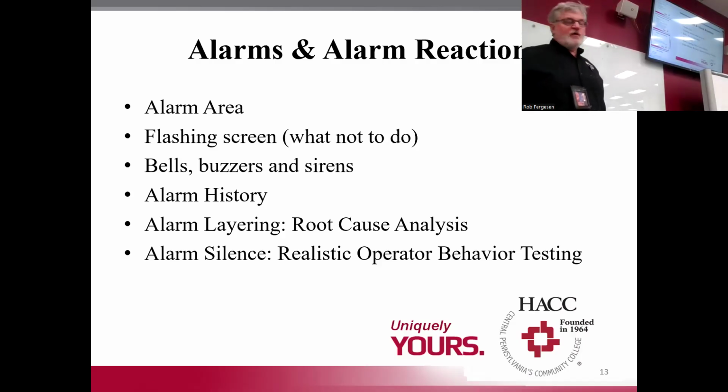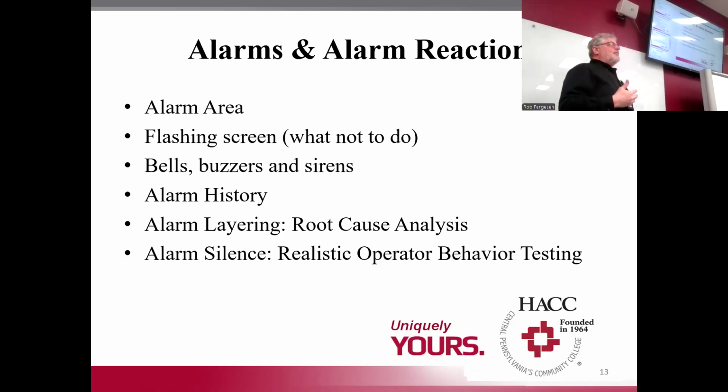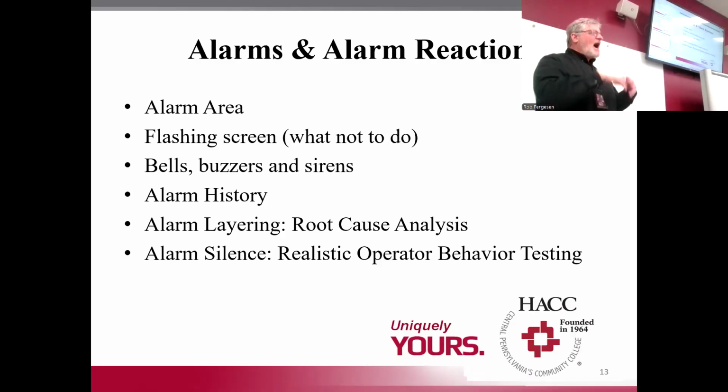The same should be true for your HMIs. You don't want a lot of flashing, buzzing, beeps and dots, and so forth. You need to design your alarms based on root cause. In other words, you can't just have an alarm for every overheat or every under pressure. You've got to think about the reasons for those alarms and build a little table deciding how those reasons can be oriented to root cause, and then allow your alarm system to give you that root cause as plausible.